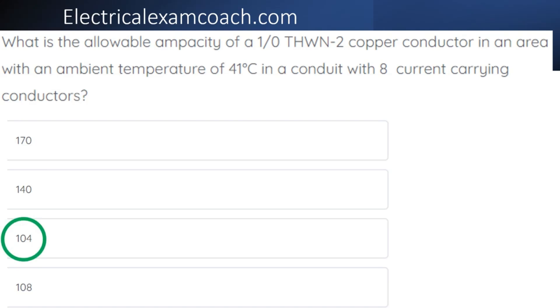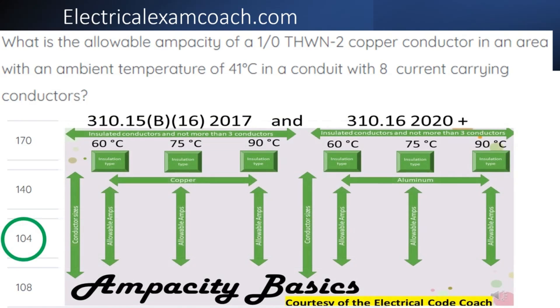The first thing we're going to do is head to our primary ampacity table. We're going to see if our insulation type is listed in the 90 degrees C column. If it is, then we're going to choose our starting ampacity from the 90 degrees C column.